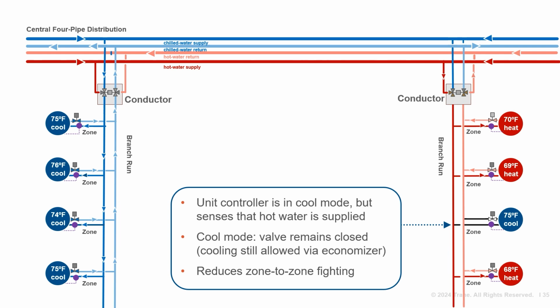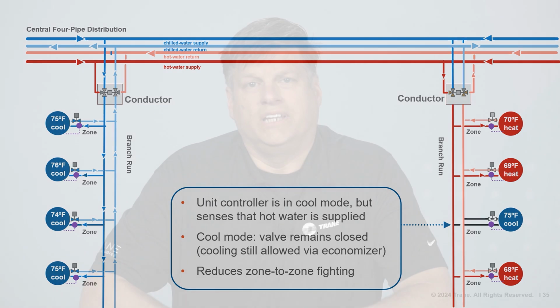This zone could cool with outdoor air by economizing. Or if this is a dedicated outdoor air system, the conditioned ventilation air could cool the zone. It may take longer to get to set point, but this will minimize the adjacent zones from fighting. The same will occur in cooling season. If one rogue zone calls for heating when it's hot outside, and the thermal area is in cooling, the unit will sense cold water and not open the valve. The space load will cause the temperature to rise in the zone. It'll just take a little longer and prevent zones from fighting and wasting energy.